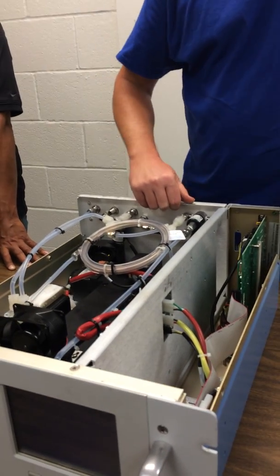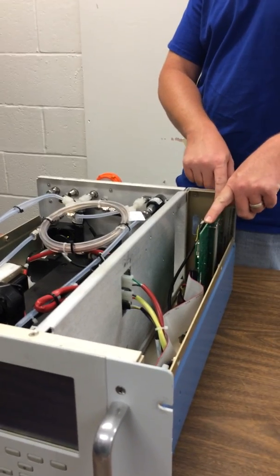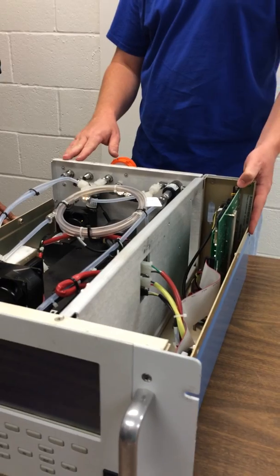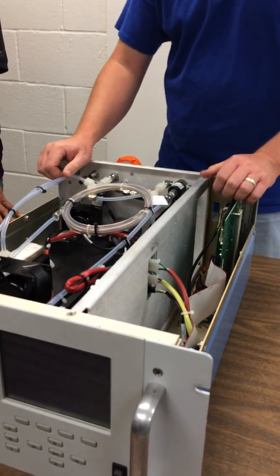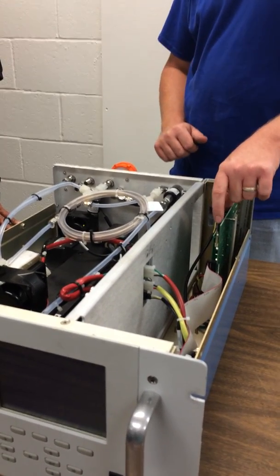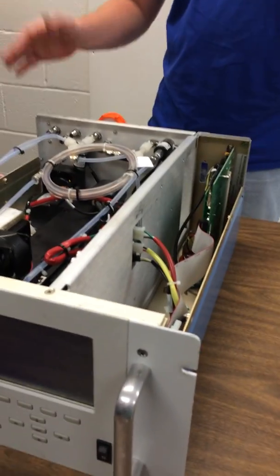The big changes for the I-Series were the power supply, kind of standardized boards, and network communications. These have Ethernet connections on them. You can put them on and drive them through the network if you want to. This is the program card for the IC. This board and this board are specific. All the other electronics in here are common to all the different instruments.